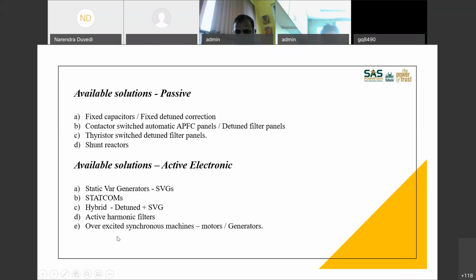Some of you might have what we call captive generation within your plant. If you have synchronous machines working in your plant, either motors or generators, suppose you have waste heat in your plant and you are using that waste heat to generate electricity, then all alternators can be programmed for partly active as well as partly reactive power to deliver into the grid. They also can be used as an active compensation device, and you can save on additional investment in your reactive power compensation systems. If it is programmed, or rather planned, during execution, it is possible.